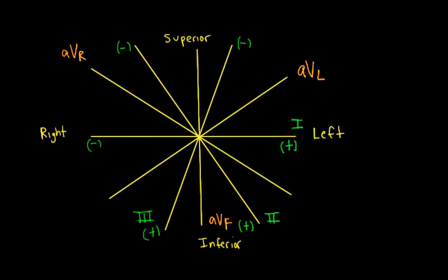For the polarities of the augmented leads: AVL takes the left arm electrode and subtracts from the central terminal, so the positive pole is on the left and the negative is down below. AVR takes the right arm electrode, so the positive pole is on the right and the negative is down. AVF takes the left leg electrode, so the positive pole is down by the left leg and the negative pole is up above.